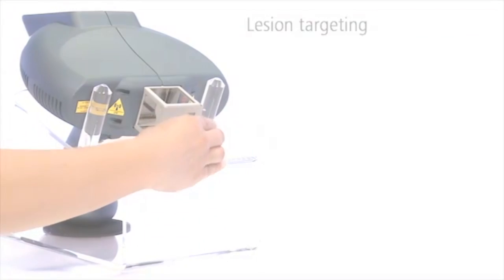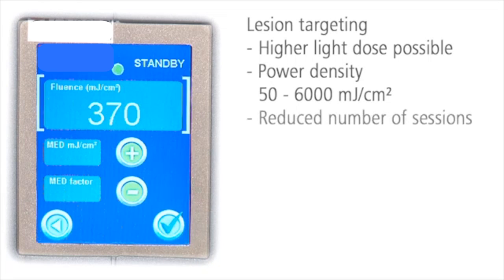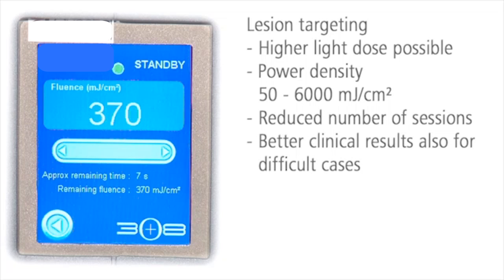Masks let you adapt the size and shape of the spot to smaller areas. Time-consuming irradiation of the full body is unnecessary. With the lesion targeting of the 308 Excimer System, you can apply a much higher dose of monochromatic UVB light. At the same time, you can reduce the total number of sessions required and improve clinical results visibly.